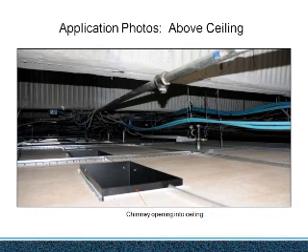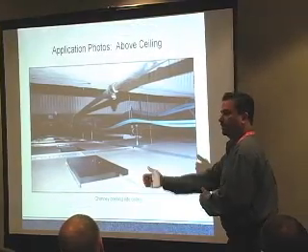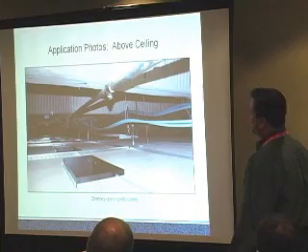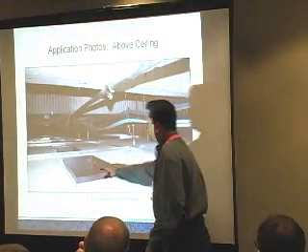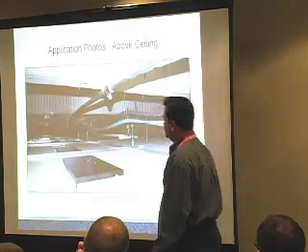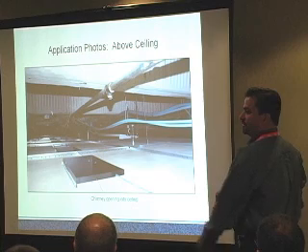And the reason why we do that is because it does jump the aisles every so often. And every time, if that was under the floor, that would be a block. What we're looking at is above the drop ceiling, where these are the hot exhaust return from the ducted return. And this whole plenum above it is the hot return.